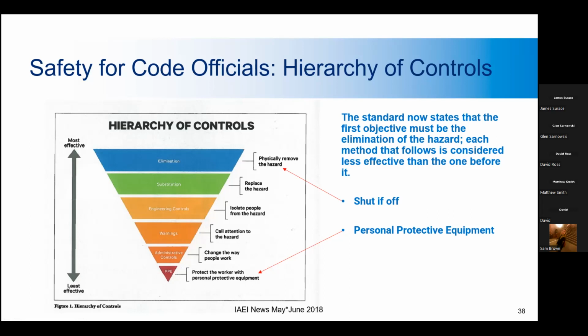So basically what that would encompass is you would shut off the power to the system and establish proper lockout tagout, and then verify that the power is off. So that way the equipment that you're inspecting is not energized, and that reduces potential human error and risk of electrical shock.